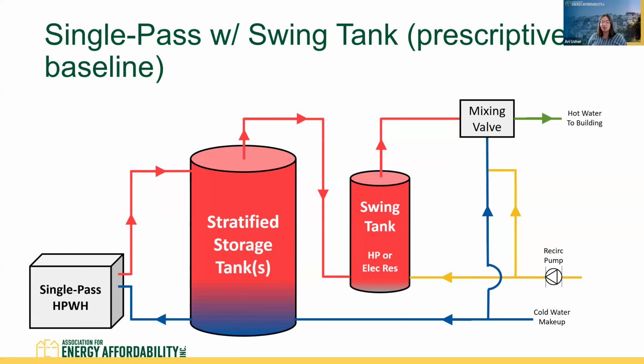So for multifamily, for these central systems, you're usually always going to also have a recirculation system. So that's where this recirc pump comes into play. When there's no demand on the system, the recirc pump is going to be circulating hot water through the pipes to keep them primed, and then returning hot water back to the system. As that water is going through the building piping, it's going to lose maybe 5 to 10 degrees of heat. And we do want to make sure to maintain the stratified storage tank, so we're not going to deliver it back to primary storage. This is where the swing tank comes in. Hot water is returned to the swing tank, and that element in the swing tank is really just for that recirculation heat loss load, to bring it back up to the set point. So that is our schematic there. Obviously, there are different configurations for multi-pass systems, but this is currently the prescriptive baseline.